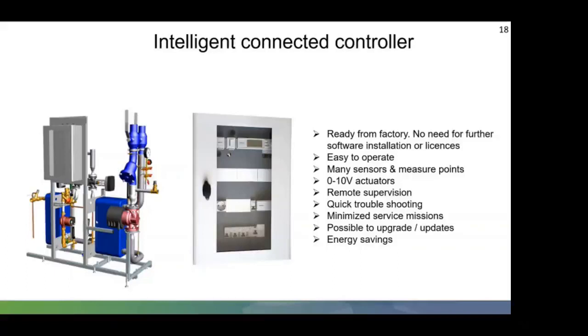By using low voltage actuators, there's decreased risk to engineers working on the substation, along with less energy used. With the intelligent controller, it gives the energy company, building management and building owners the ability to view, and with the correct given access, adjust the substation without having to attend site. So again, it makes it easier if you get a warmer day in the winter, or a couple of warmer or colder days, you can actually change the heat flow and return just by tweaking it via the BMS panel.